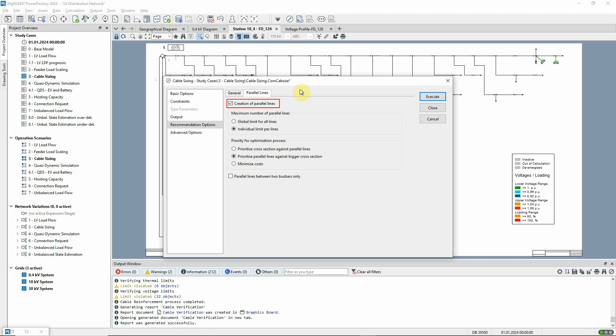The option selected here means that creating parallel lines will be the first choice and only if the maximum number of parallel lines does not solve the problem will the cable cross-section be increased.